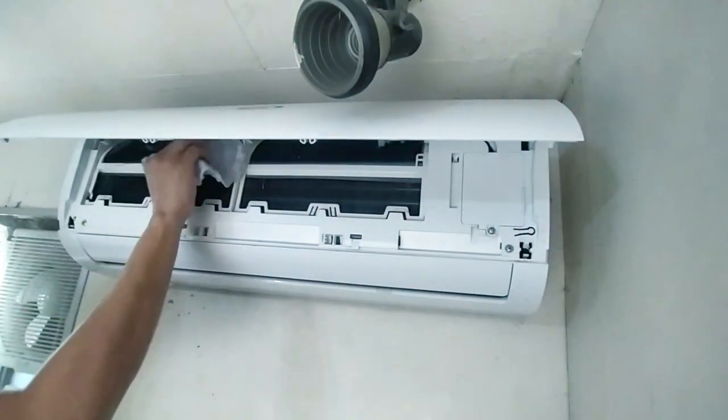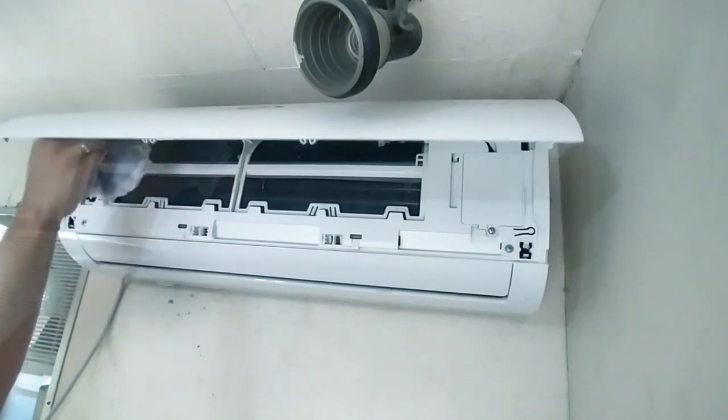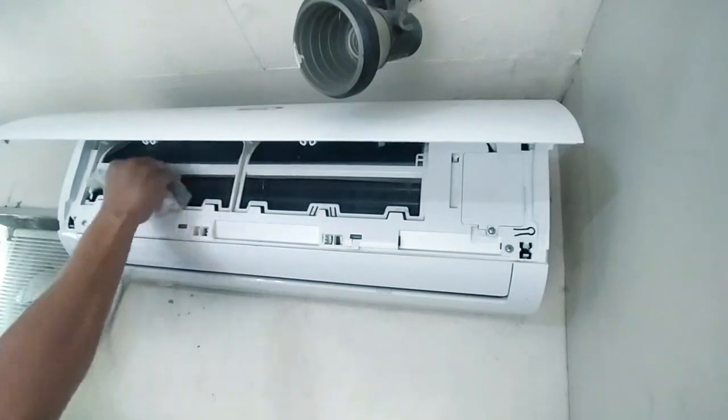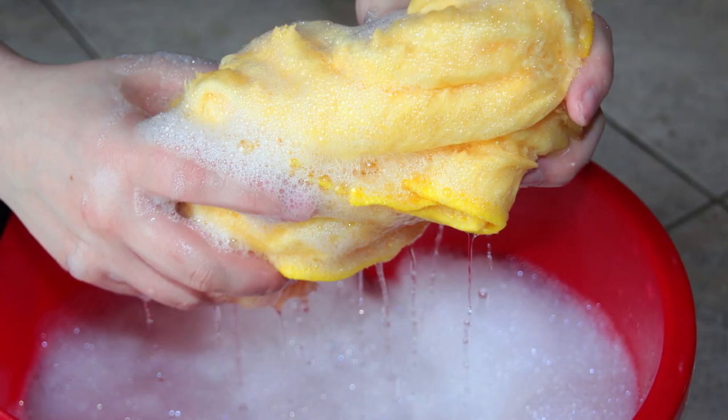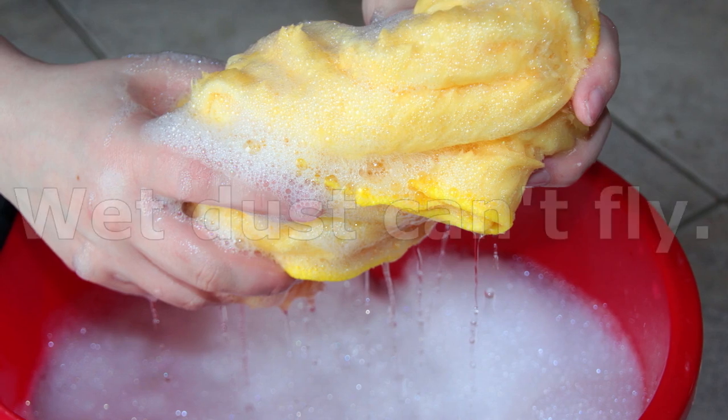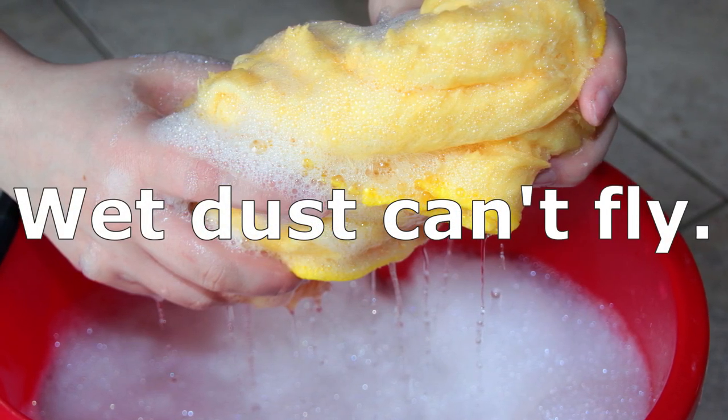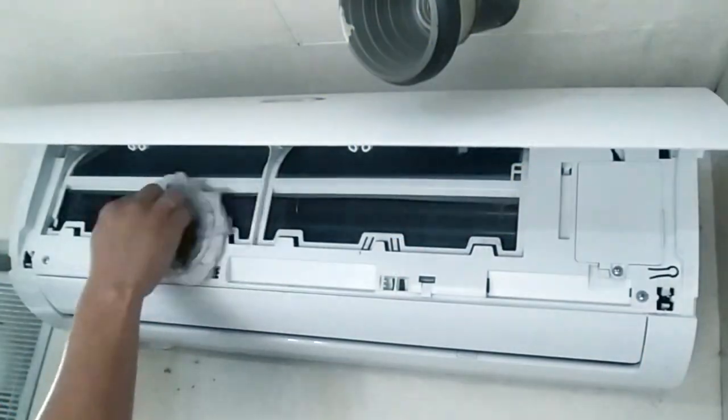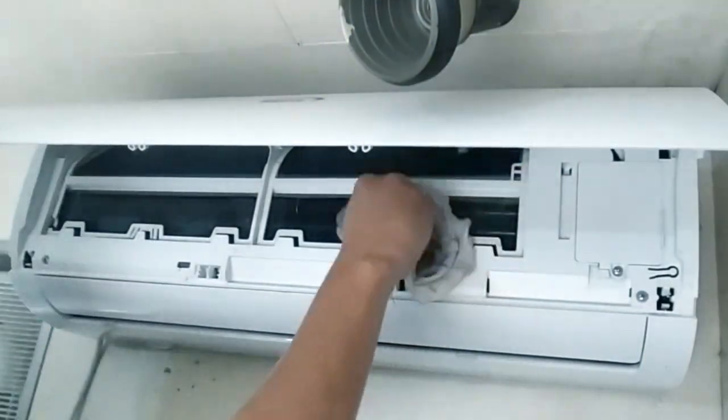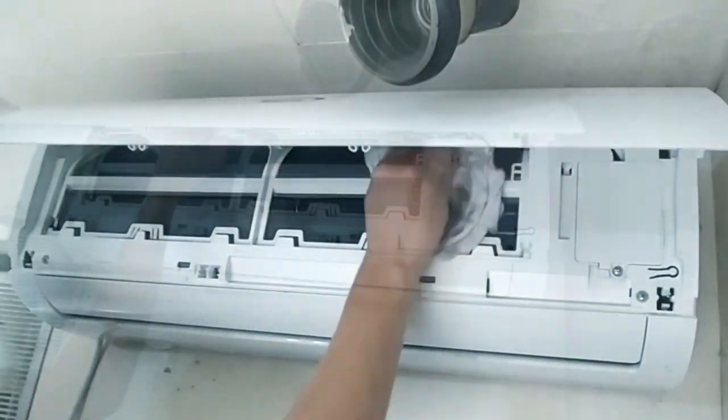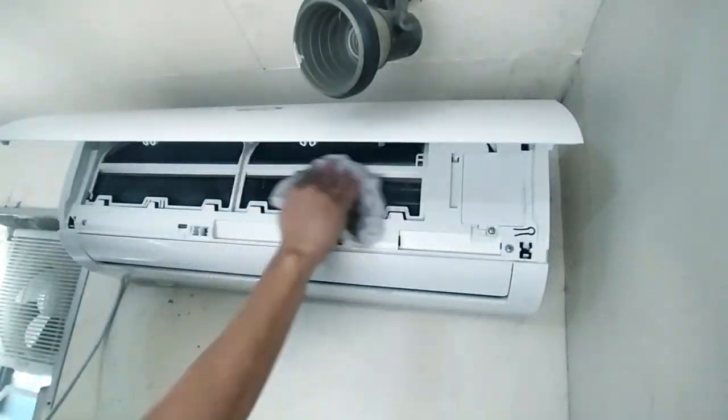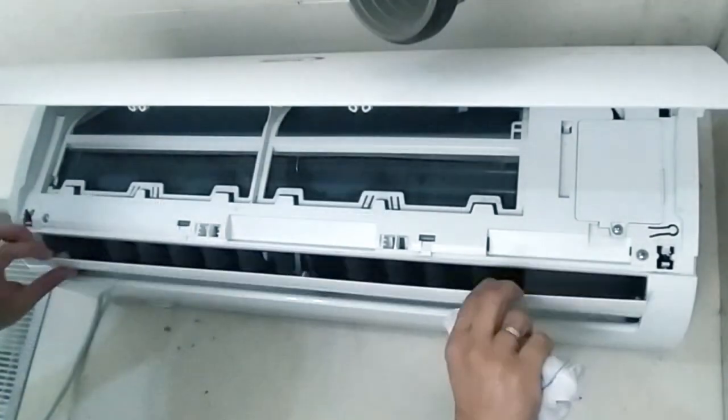You might be wondering why do we need to use a damp cloth? It's because if we use a dry cloth or even a brush, we'll just be agitating the dust particles and cause them flying around the room. So think about this, wet dust can't fly. Also, focus on other parts where dust and grease can accumulate such as the fins, underneath the front panel, and the louvers.